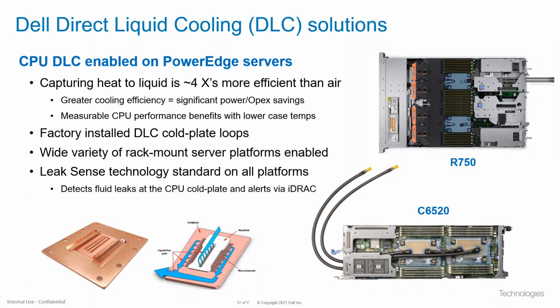The lower solution is what's called our C6520, which is our 15th generation server node that goes into a 2U chassis. 4 compute nodes will fit in this 2U chassis. So it's our densest solution, very popular with high performance compute deployments. In both cases, the cold plates consist of the tubes, the cold plates that attach on top of the CPUs that replace the air heat sinks, and then those lines connect to rack manifolds in the back of the rack.